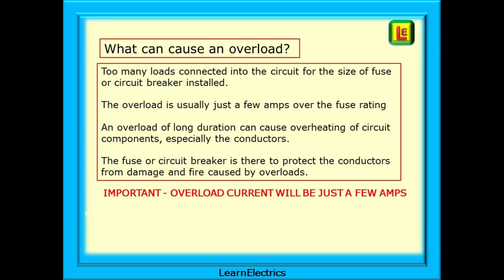So we know now what can cause an overload. It is too many loads connected into the circuit for the size of fuse or circuit breaker that is installed. Usually, this overload is only a few amps over the fuse or breaker rating. If the excess load is removed after just a few minutes, then most times the circuit will settle itself down again without actually tripping and the customer will have no idea that there was an overload.